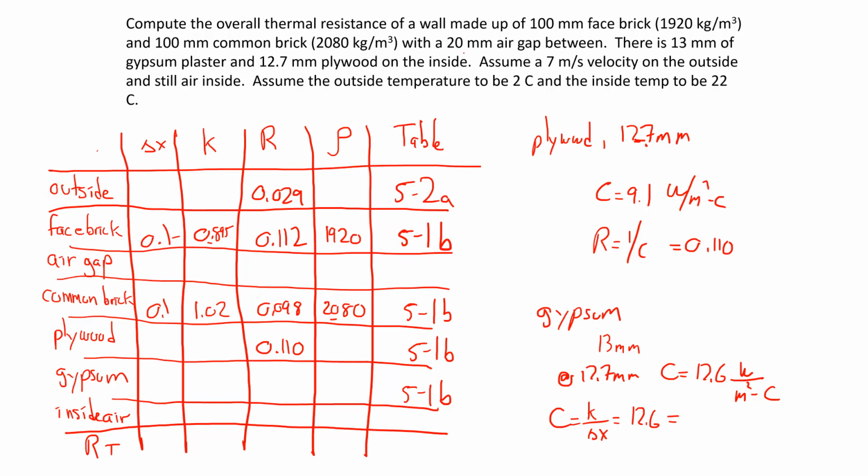That's the effective emissivity between the two surfaces that encapsulate the airspace. In that case, 0.82 would be the highest emissivity value, resembling a dark surface, which is what a brick would be. And so you should end up with 0.17 as the air gap thermal resistance. I know that was a lot to go through.